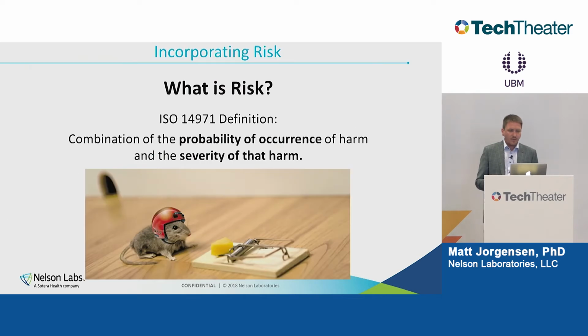When we talk about risk in this context, this comes from ISO 14971. It's the combination of probability of occurrence of harm and severity of that harm. The reason I want to point this out is because when we're going through this process of trying to pick which biocompatibility tests are really needed, it's important to think about risk this way, because we get people concerned about risk across the spectrum.